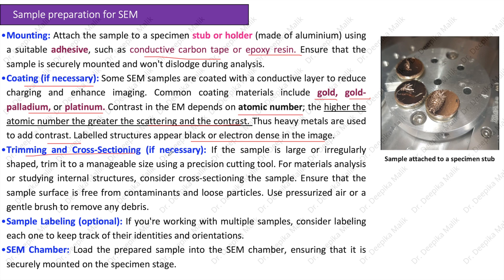Trimming and cross-sectioning, if necessary: if the sample is large or irregularly shaped, trim it to a manageable size using a precision cutting tool. For material analysis or studying internal structures, consider cross-sectioning the sample, ensuring the surface is free from contaminants and loose particles — use pressurized air or a gentle brush to remove debris. Sample labeling is optional: if working with multiple samples, consider labeling each to track identities and orientations. Finally, load the prepared sample into the SEM chamber, ensuring it is securely mounted on the specimen stage.